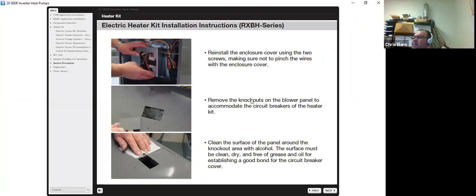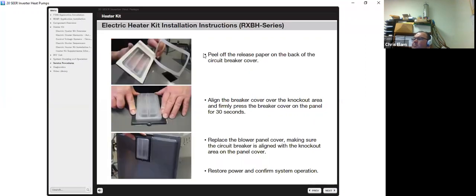Remove whatever knockouts on the blower panel to accommodate the circuit breakers of the heater kit. Clean the surface of the panel around the knockout area with alcohol. The surface must be clean and dry and free of grease and oil to ensure the cover bonds correctly. Peel off the release paper on the back of the circuit breaker cover. Align the breaker cover over the knockout area and firmly press the breaker cover for 30 seconds to secure. Replace the blower cover, making sure the circuit breaker cover is aligned with the knockouts on the panel. You can restore power, and you're good to go. Remove the cover.